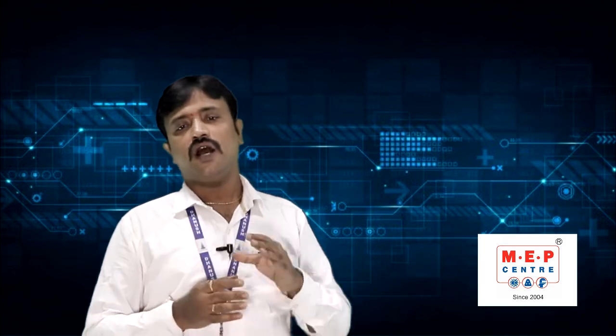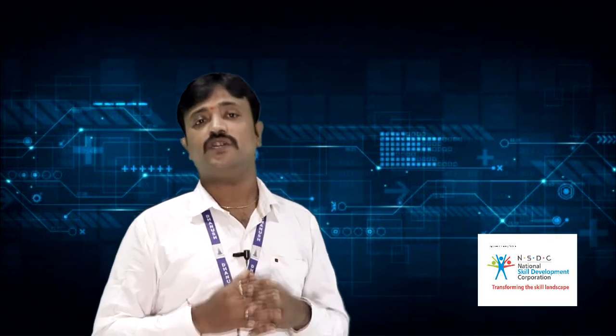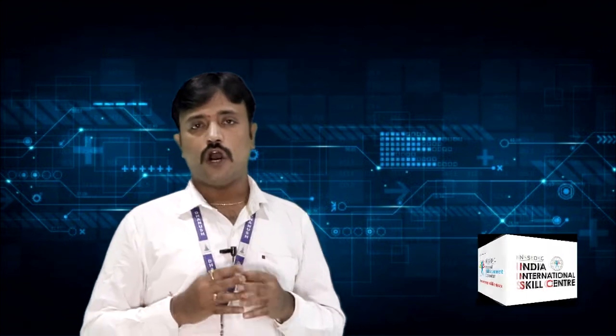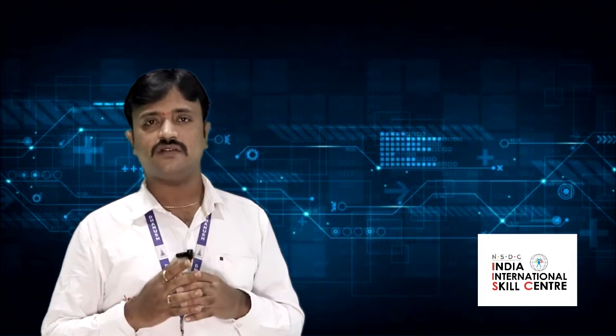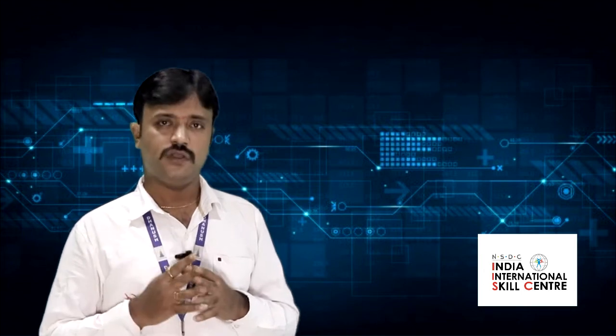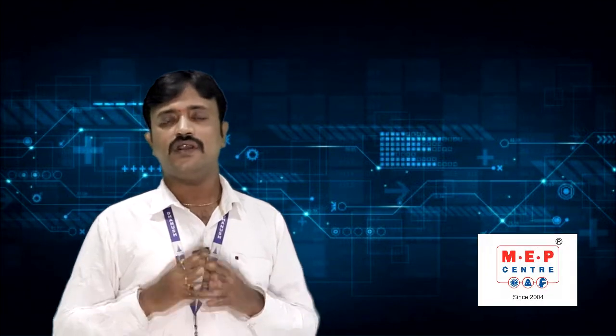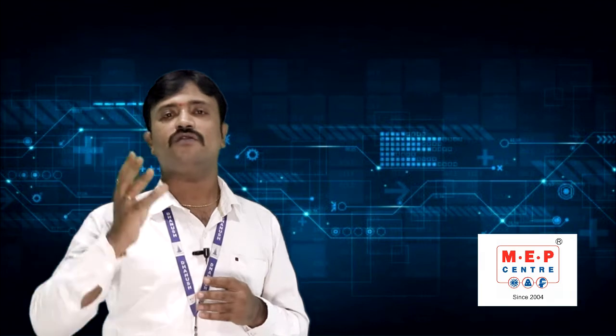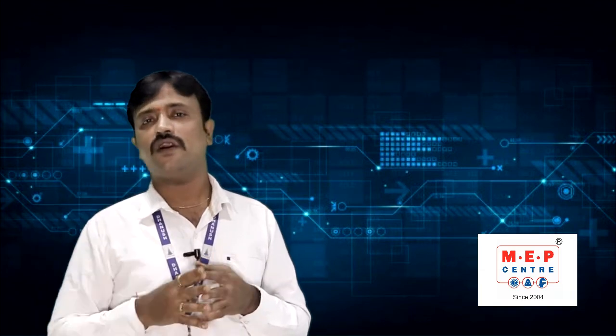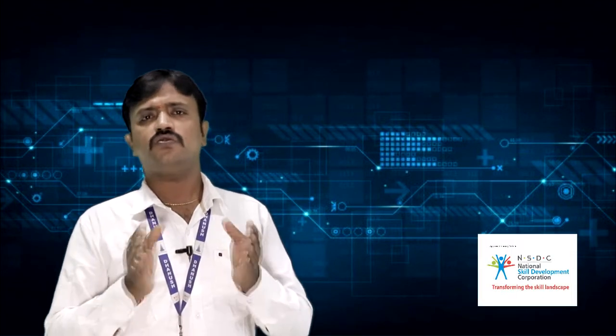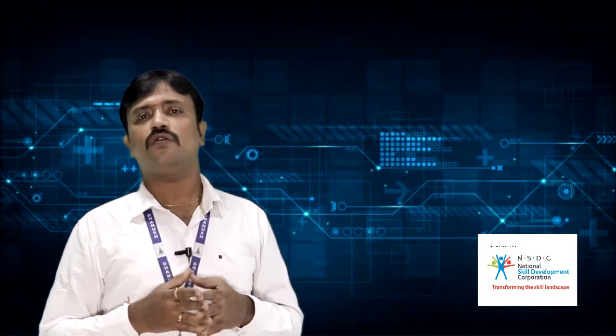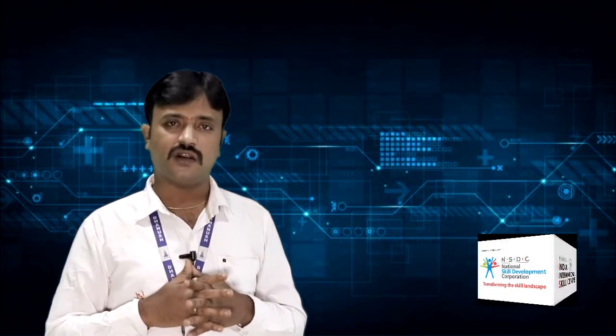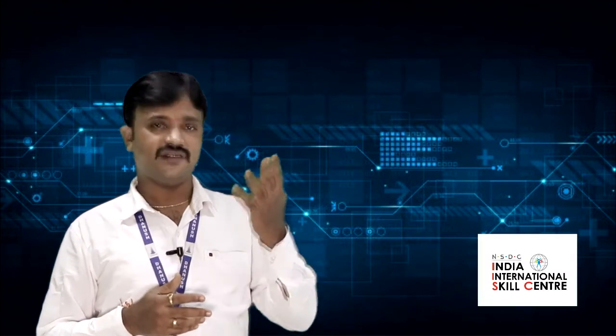Okay, done. Now up to here we have done the design. The next thing is we need to do analysis of whether your design is perfect or not. So how do we analyze? What are the parameters we require for analysis? The most important parameter is voltage drop. We need to consider the voltage drop, because if my transformer is far away from your building, and I need to supply to all ten floors, and I'm not getting sufficient voltage to run your fan, like we require 230 volts and you are getting 110, then there is no use of your design. So to get 100% voltage at each and every point, we are going to study a calculation called voltage drop calculation, which depends upon the length and resistance of the cable.